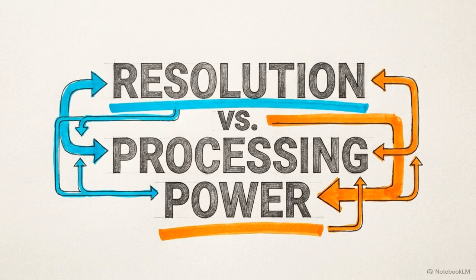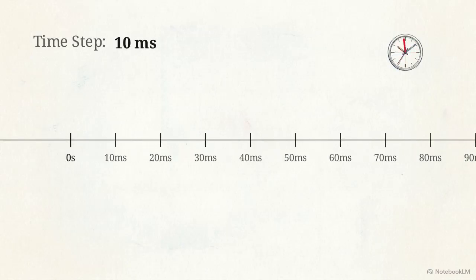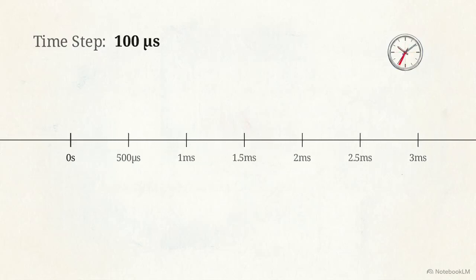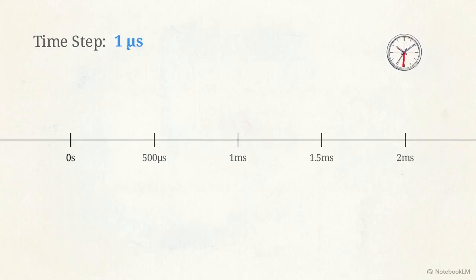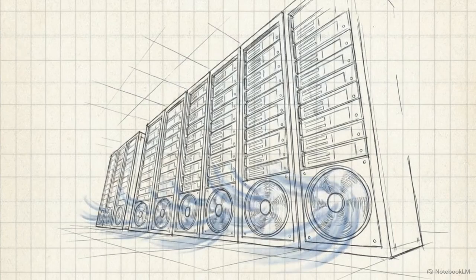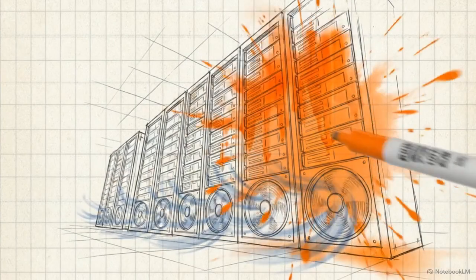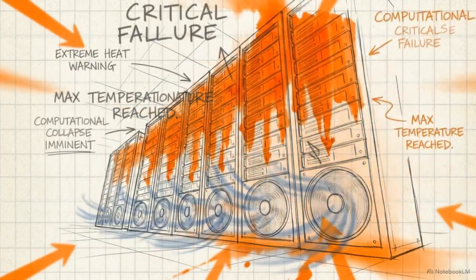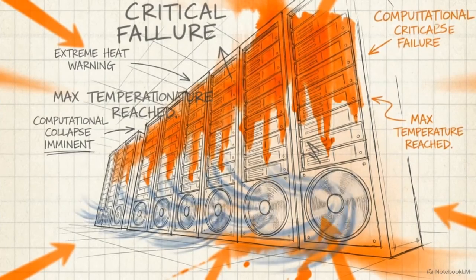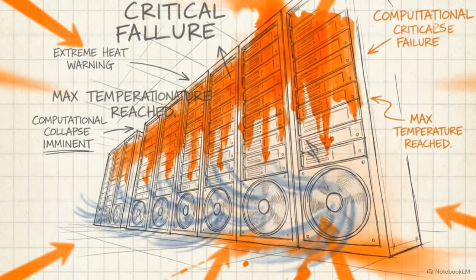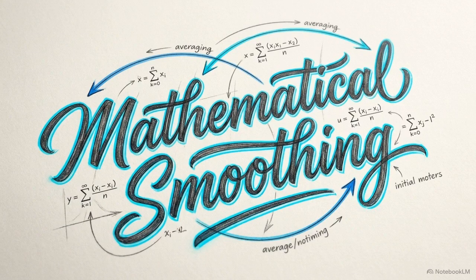Once the data is collected, modelers face a strict computational limit, the resolution to computation trade-off. The highest fidelity representation is the switching model, which calculates electrical behavior at microsecond intervals. Applying a switching model across thousands of converters in a 200-megawatt facility causes a computational collapse. The processing power required is too high. To make bulk grid studies feasible, the industry uses the average value model.